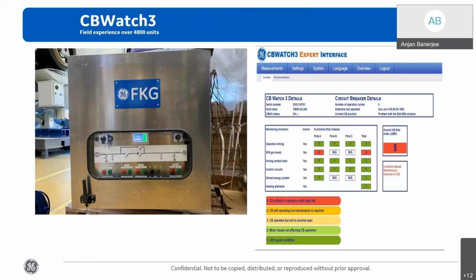This expert software analyzes the risk of every element, and depending upon the analysis, it would attach a risk level index. Say, for example, as we can see over here, in this particular case, the circuit breaker SF6 gas level density has gone below threshold 2. So then the device would alert the user with a risk index of 5. That means the circuit breaker can no more be continued in service. It has to be taken for maintenance. So this is actually a truly condition-based maintenance solution offered by GE to customers.